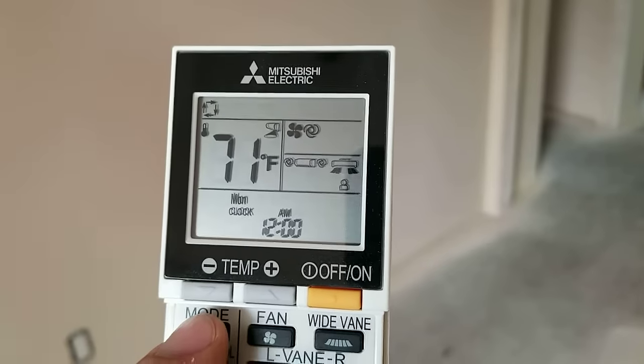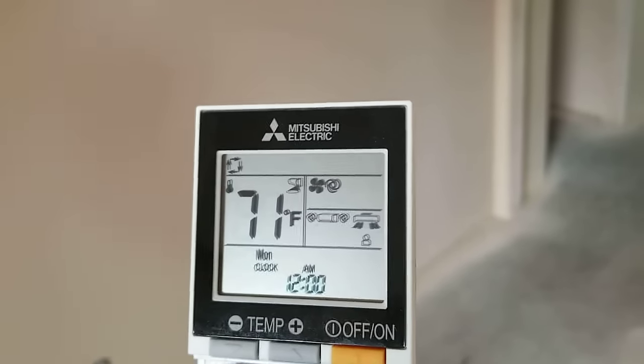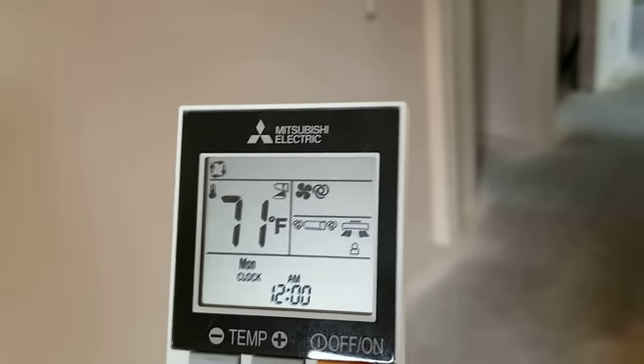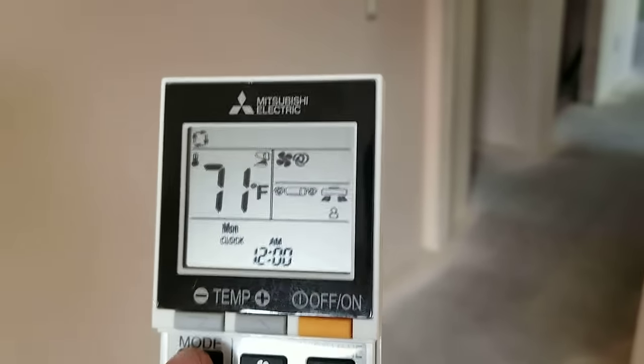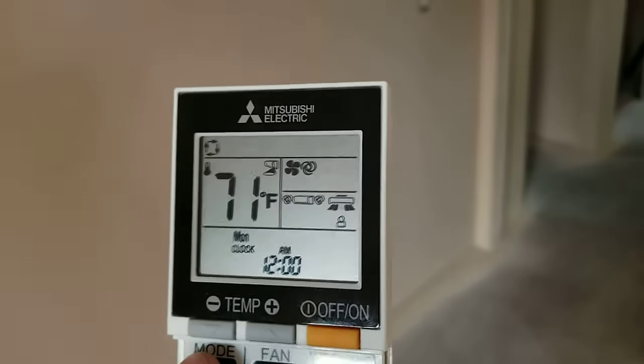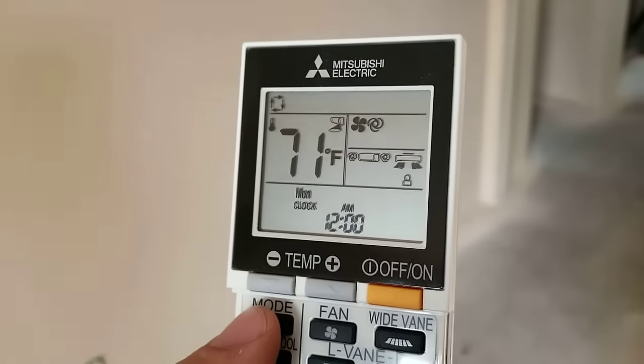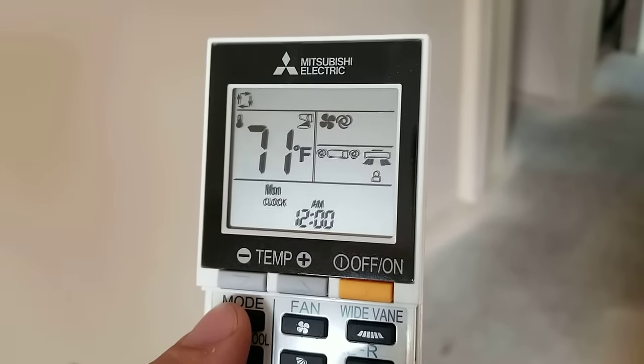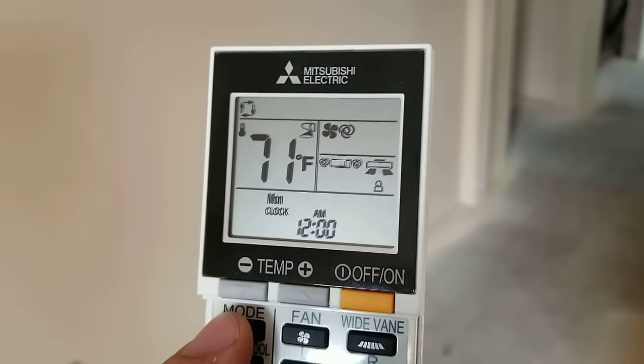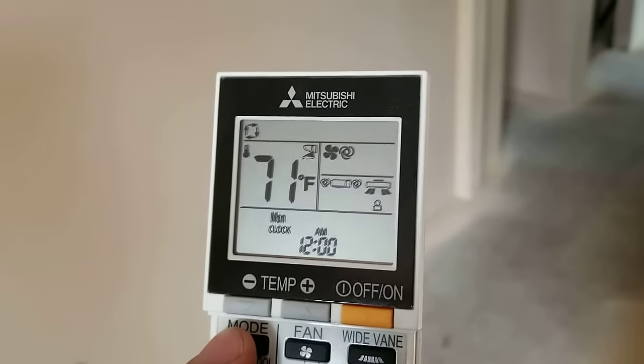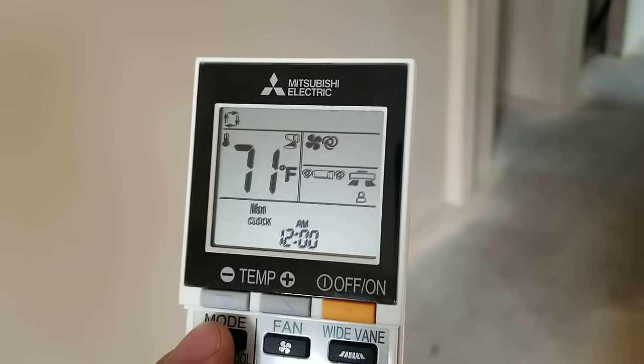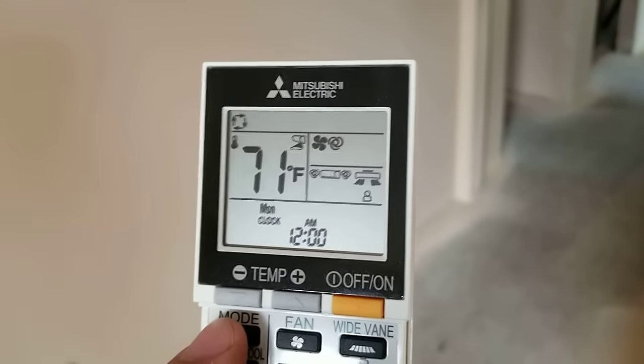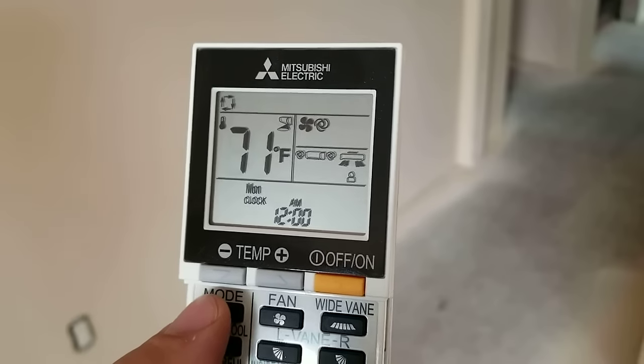What can happen, the unit will either heat or cool the space to maintain that temperature that you're putting in. Now, the only drawback with that is that in most cases, there's going to be a four and a half degree Fahrenheit variance from that set point.